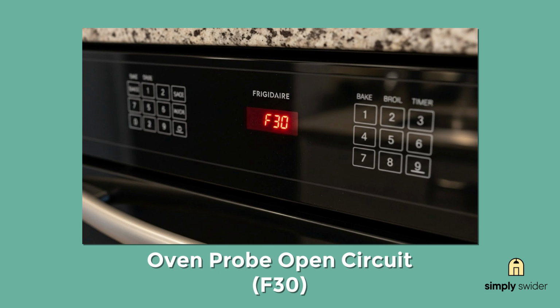Here's the quick breakdown. F30 on your range means a disconnected temperature probe. On refrigerators, you'll see either OP, meaning sensor disconnected, or SH, meaning sensor shorted out. You'll notice your appliance isn't maintaining proper temperatures, either too hot, too cold, or all over the place.